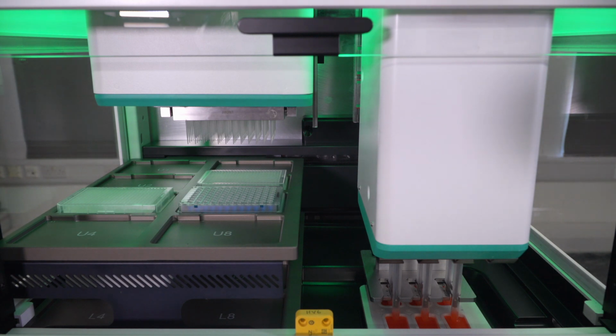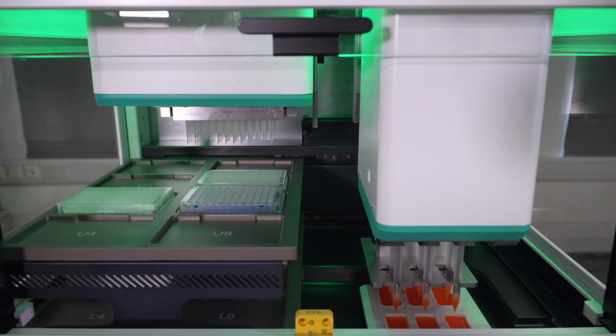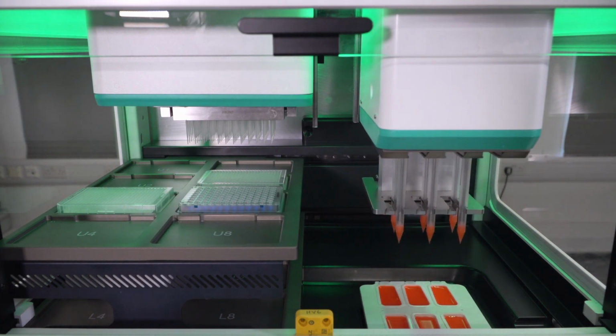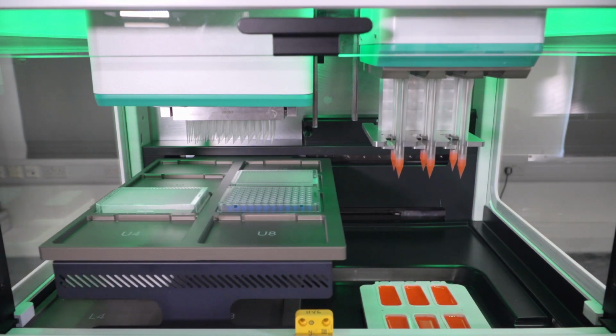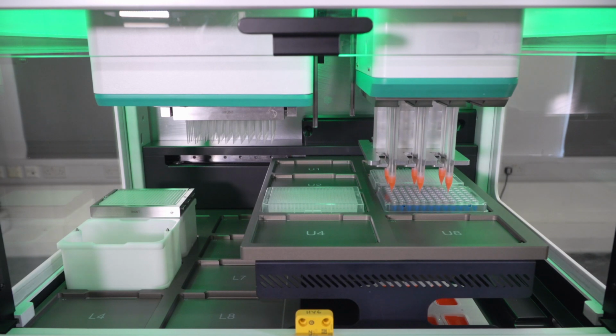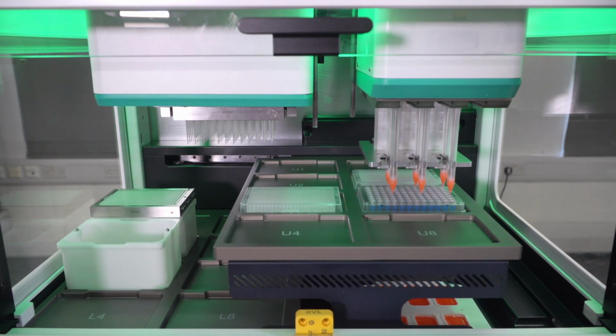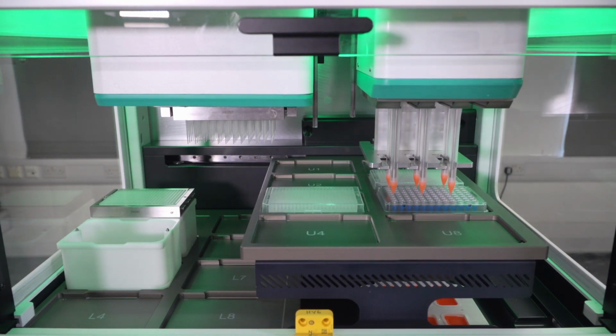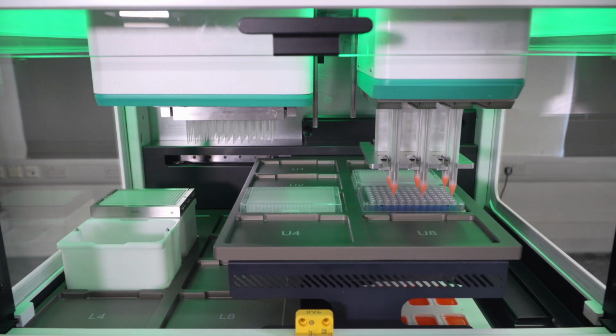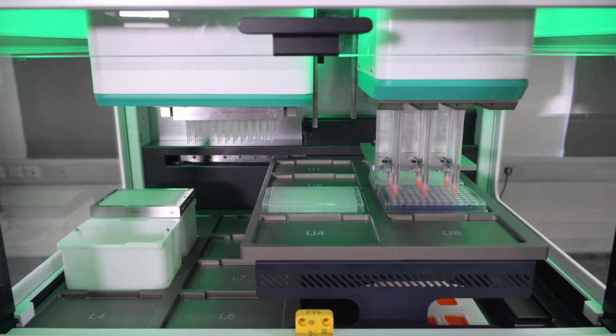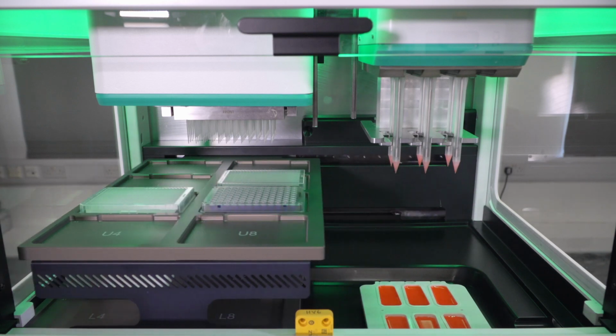Here we're going to actually use multiple syringes, six syringes in total with the same reagent, but you've got a complete choice over how many syringes that you use. And it's simply a question of dead volume versus speed. So you can see here with all six syringes dispensing simultaneously, it's extremely quick. And that's a 96 well plate dispensed to already.